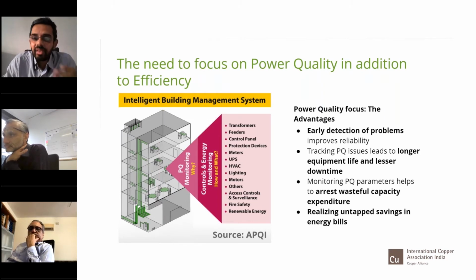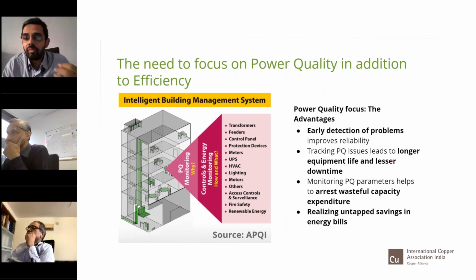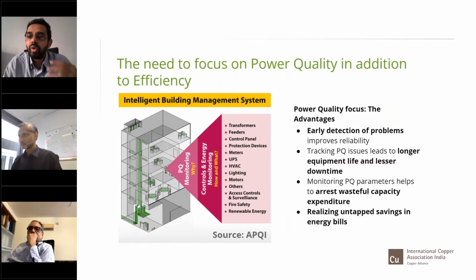This is something that can be detected earlier with proactive monitoring of power quality. If you're talking about tracking PQ issues leading to longer equipment life and lesser downtime, this benefit comes from monitoring harmonics and taking corrective actions much earlier. For example, it can enhance the life of capacitors and conductors, with lesser heating of loads and hence longer lifetimes.